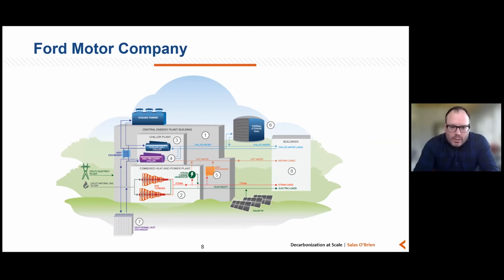There's also the 5 million gallons of thermal energy storage that is a chilled water storage tank in this setting. Again, that gives us more runtime on certain assets and the ability to dispatch in a much more flexible way a collection of very complicated assets in that central energy plant.